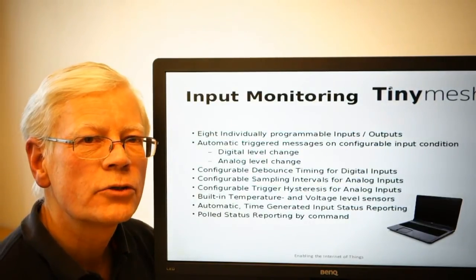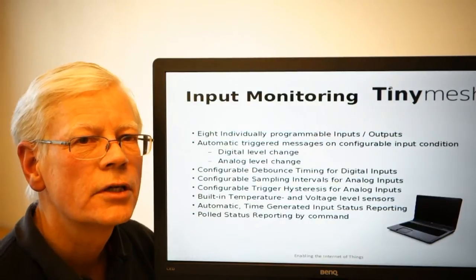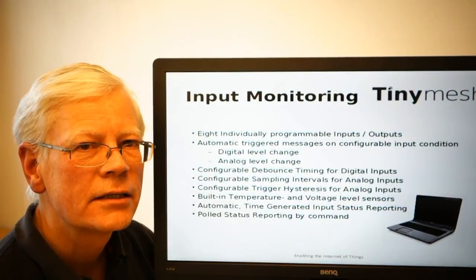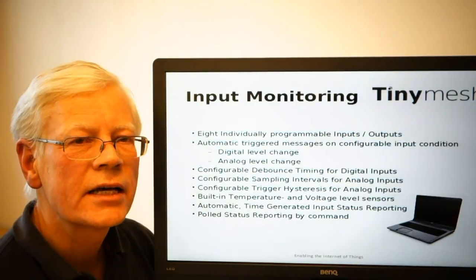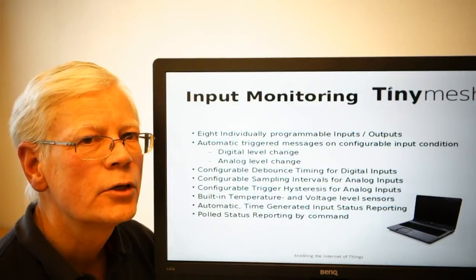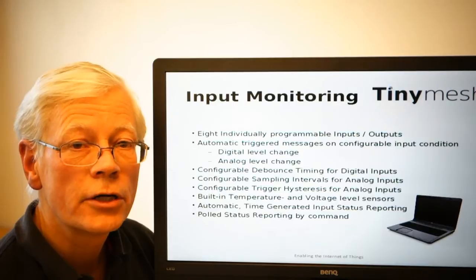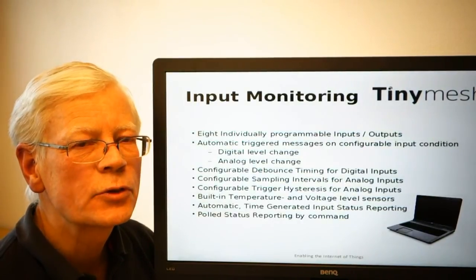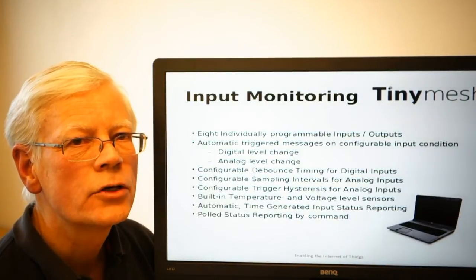When set to analog input, you may also set trigger levels on the analog ports. You have both a high and a low analog threshold that may be individually set. With both a high and a low threshold, you have created a hysteresis window, which means that you can set the ports to trigger messages when the analog signal travels from above the high level to below the low level, or from below the low level to above the high level, or on transition in both directions.